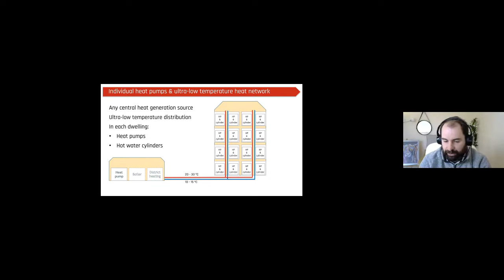So from an engineering perspective, when I look at them, I have these risk items that I'd like to review. The capital costs of the systems, and the operational costs, which are made up of a lot of factors: the utility costs of what you're paying for your electricity centrally or in the dwelling, or any other utility costs, which could be gas. Maintenance, both within the central plant and within the dwelling. Thermal storage, its size and ability to use it to react to price and carbon changes. Heat losses from both systems, pumping energy, and plant efficiency. And what choice of centralized plant you have and what ability you have to upgrade it in the future.